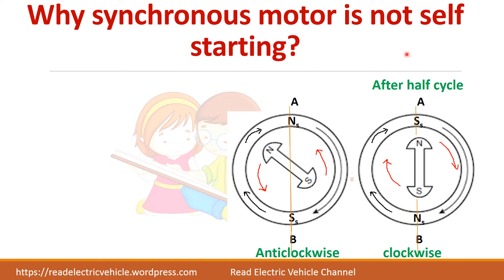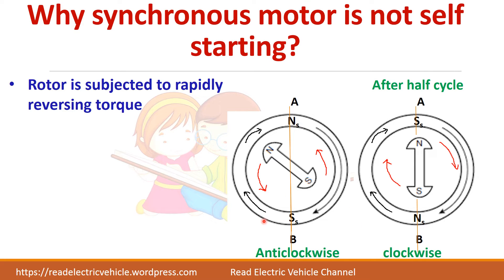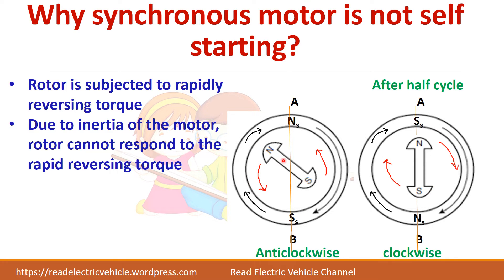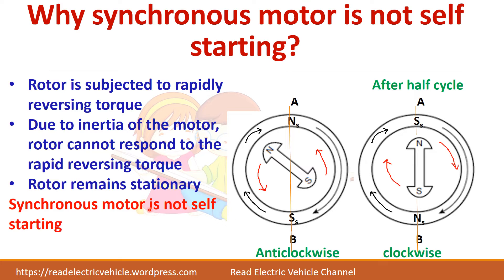In the next half cycle it again rotates in the anticlockwise direction. So it is subjected to a rapidly reversing torque — it is going in one direction for some time, then the opposite direction for some time. Due to the inertia of the rotor, the rotor cannot move and it remains stationary. So we say that synchronous motor is not self-starting.